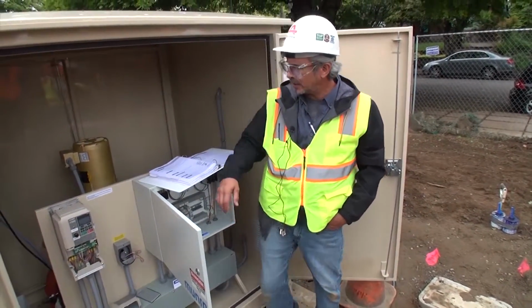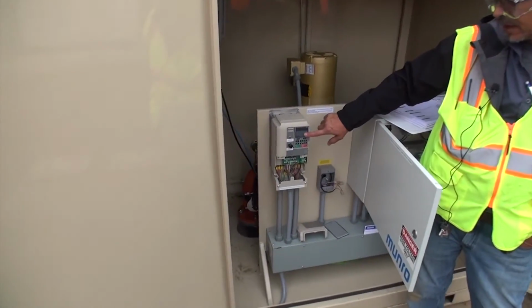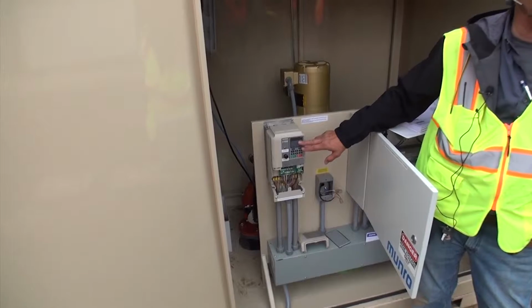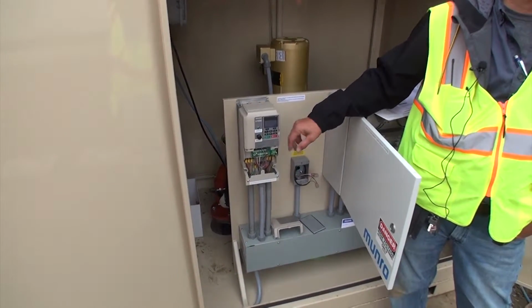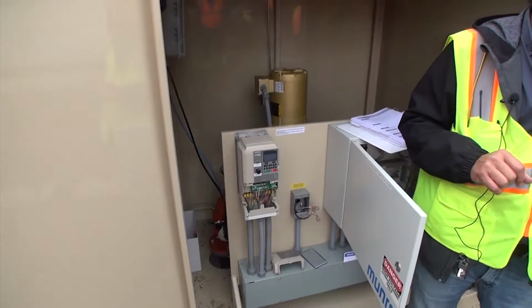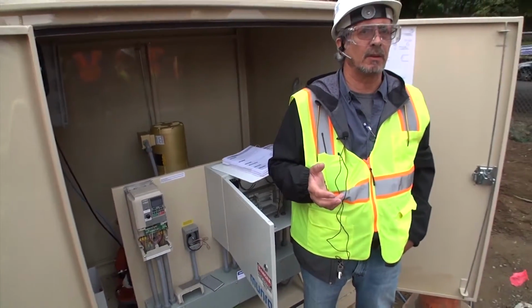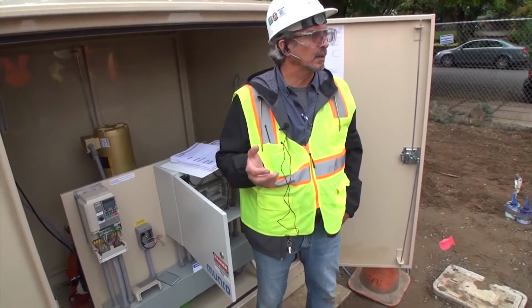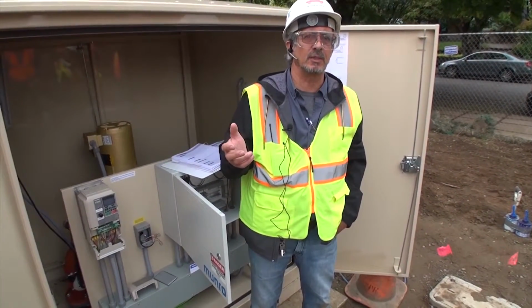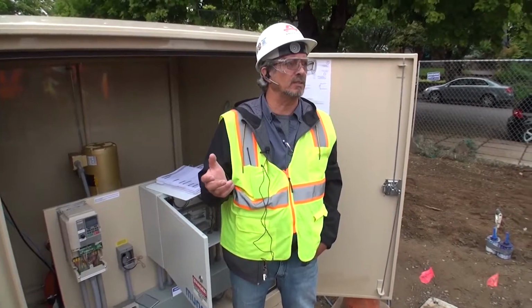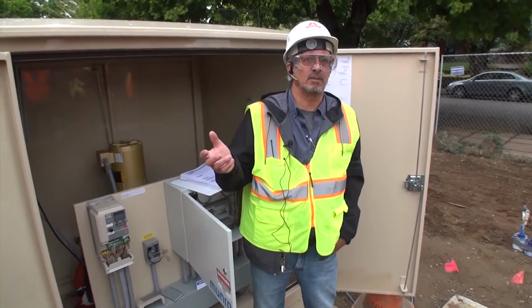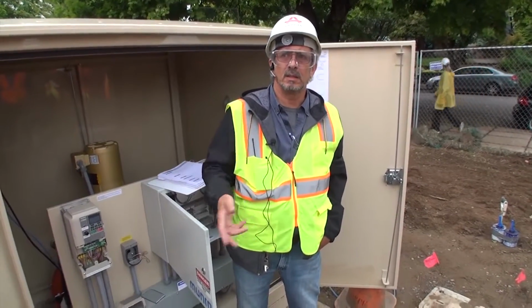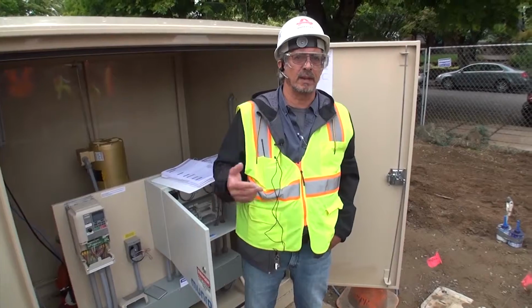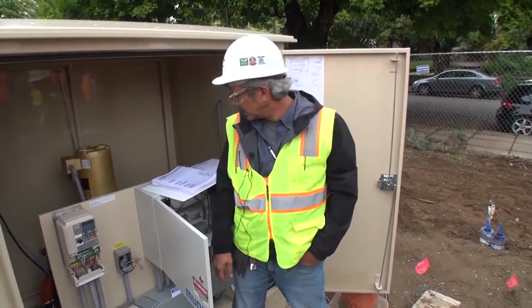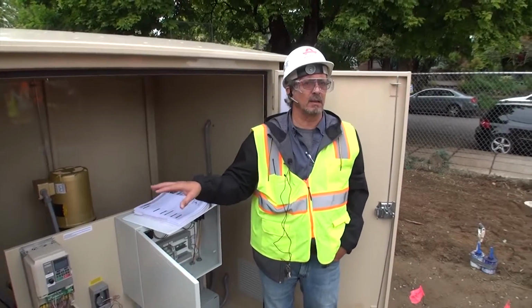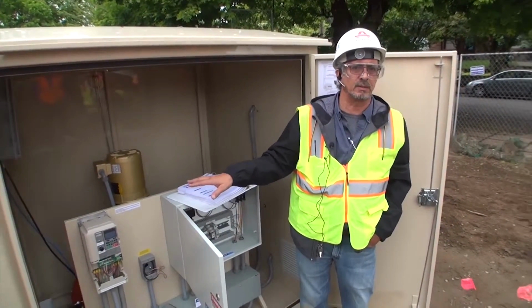If you wish to record user data, see how it says alarm and it says sleep? You can't really see much. If you flip that off, now you can get to this display here. The U4s in here are your maintenance things. If you actually want to keep track of how many hours you have on it, it has a log in there for what your usable life expectancy is for the drive. It works like the odometer in your car with the oil changes. It starts out that you have 100% of life left, and it just counts down gradually according to how many hours they think the capacitors are good for, the fan is good for, and everything else. If you wish to go through that, I recommend you call me, because that's another conversation in and of itself.